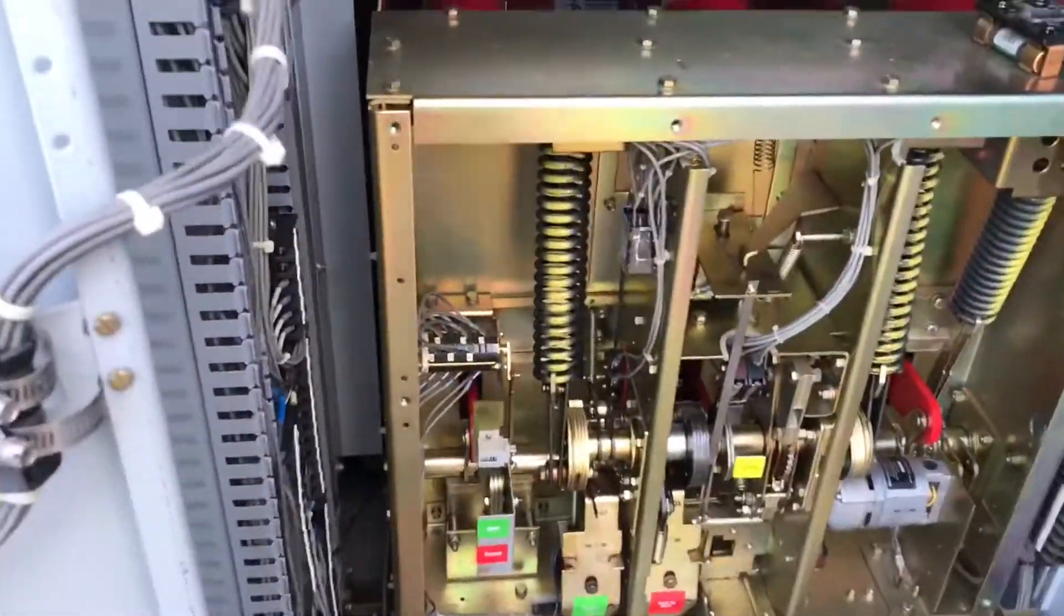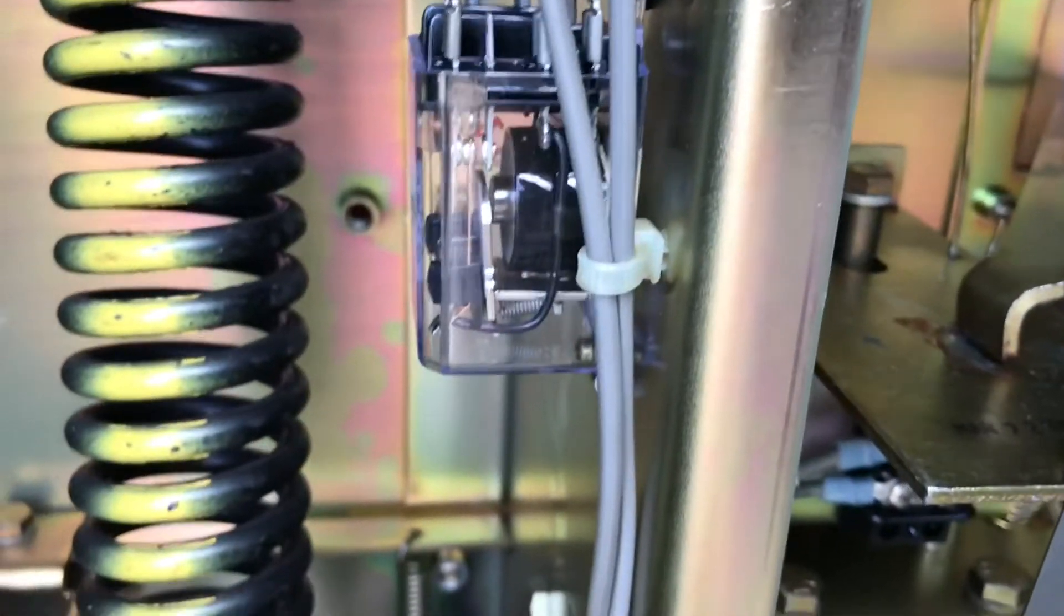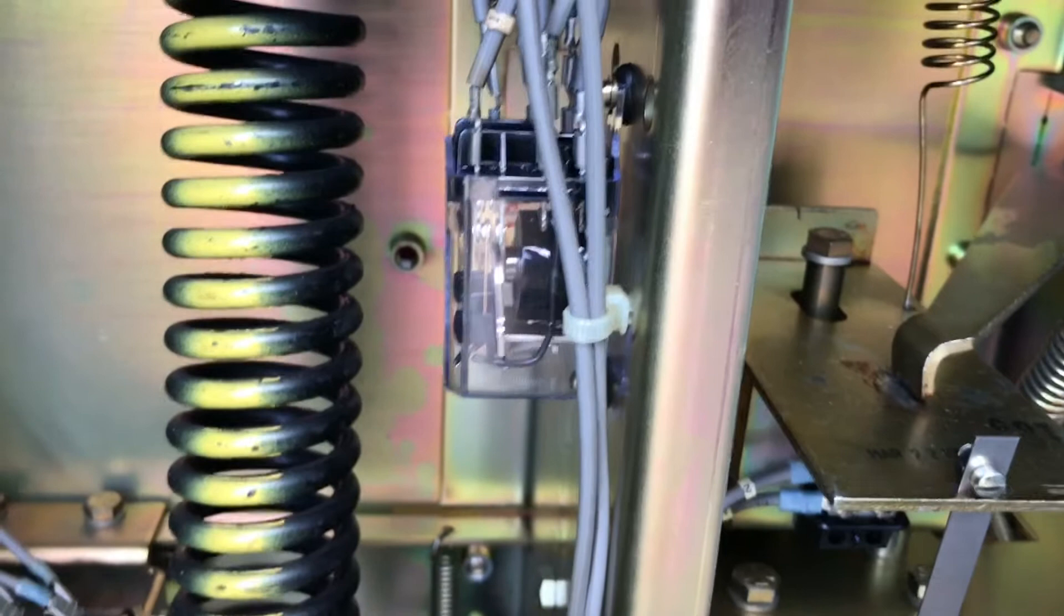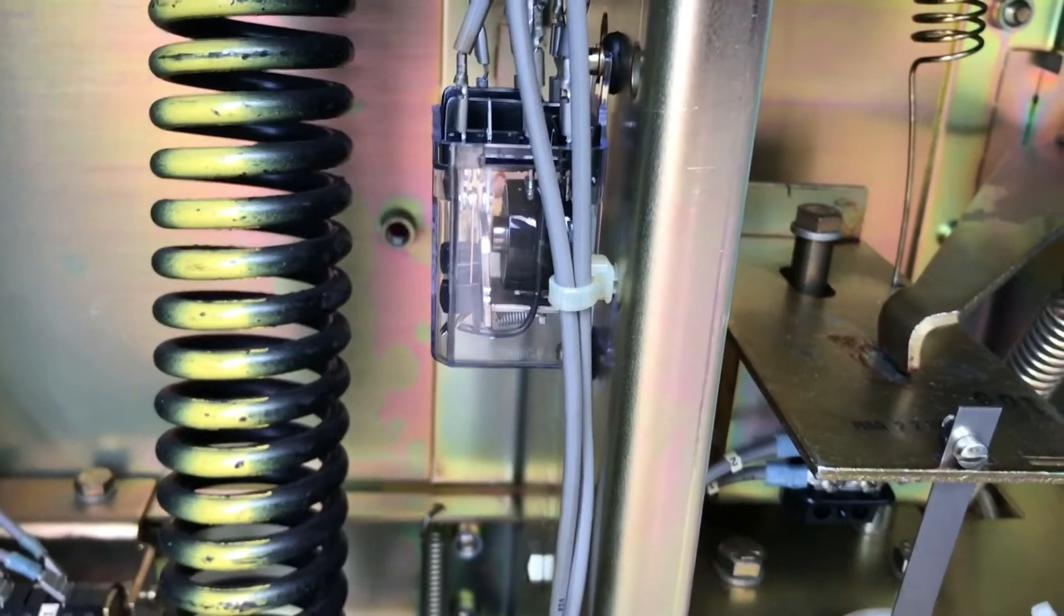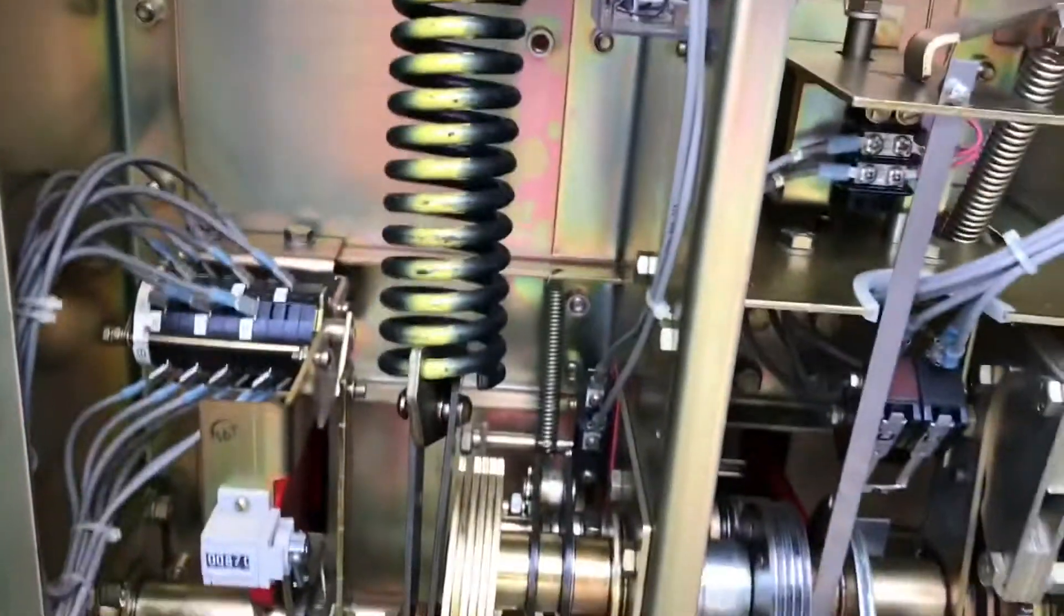One more thing to note here—I should have looked at this—is the anti-pumping relay. So once I turn the control switch, that will energize and that will remain energized until the closed switch contact opens again. So I'm going to try my best to simulate that here.